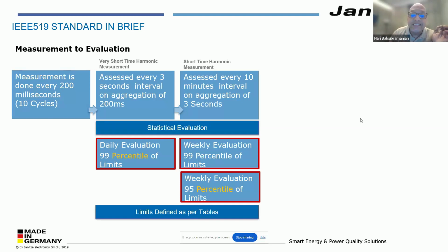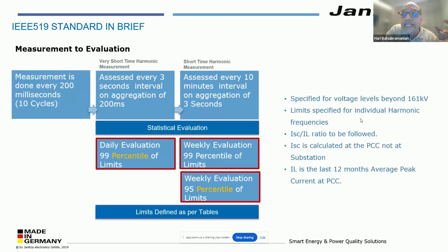Why we have these three values is the next question. Why should we do three statistical evaluations in these calculations? When the standard was formed, they wanted to make sure that every kind of load adheres to it. A constant load can very easily pass the 99th percentile daily values, but on weekly values it can potentially fail. For example, a textile unit can probably pass the 99th percentile evaluation limits, but might have trouble with the weekly evaluation limits with 10 minute values, or vice versa for a furnace. In a furnace industry, it can probably fail on the 99th percentile, and it can also sometimes pass on the 95th and 99th on a weekly evaluation.